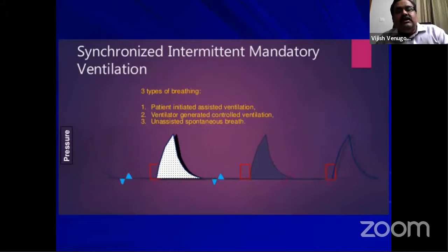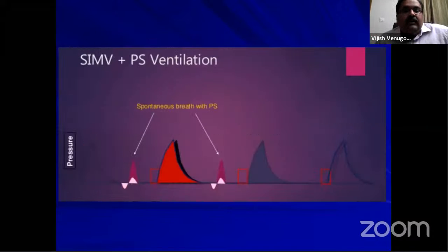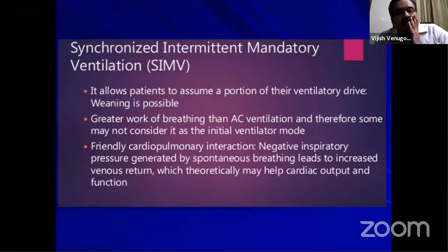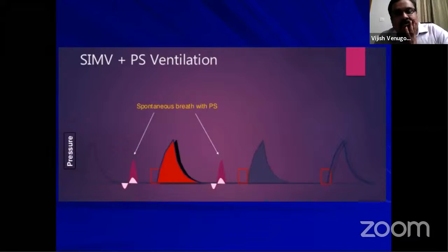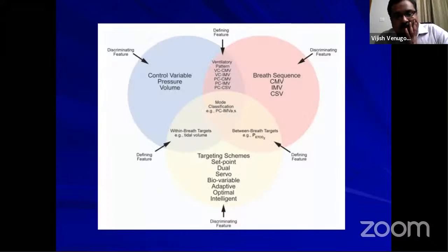So ultimately, in synchronized intermittent mandatory ventilation, you will have three types of breathing. One is the patient-initiated assisted ventilation, shown in white, the ventilator-generated controlled ventilation, shown in blue, or rather grayish color, and the sinusoidal one, which is the unassisted spontaneous breath. So there are three different types of breathing in synchronized intermittent mandatory ventilation. However, remember that there is a great work of breathing during this mode. So it is always advised that you add pressure support to synchronized intermittent mandatory ventilation.